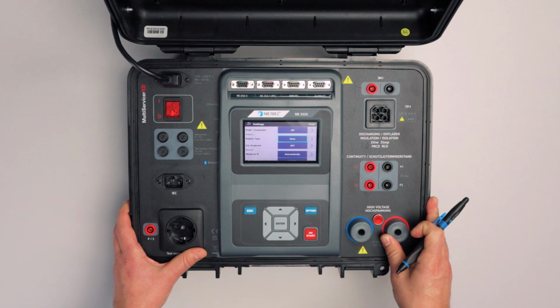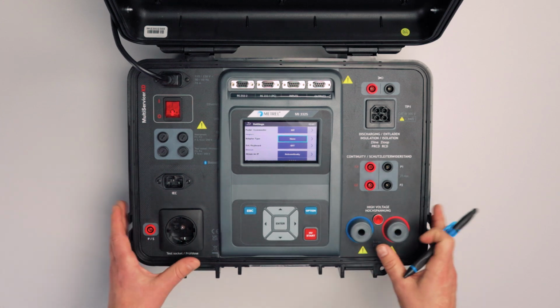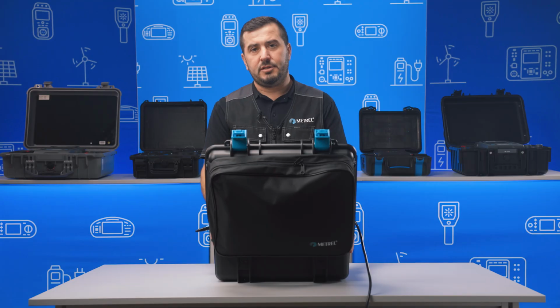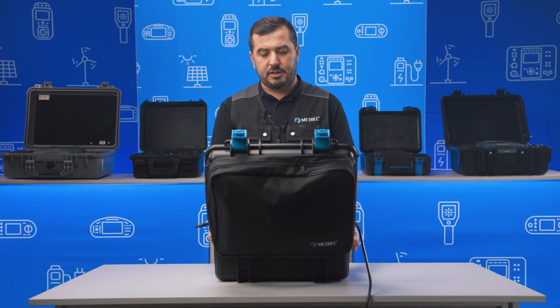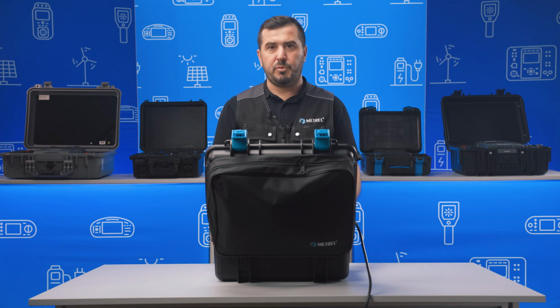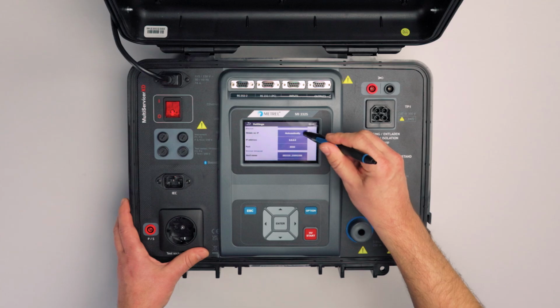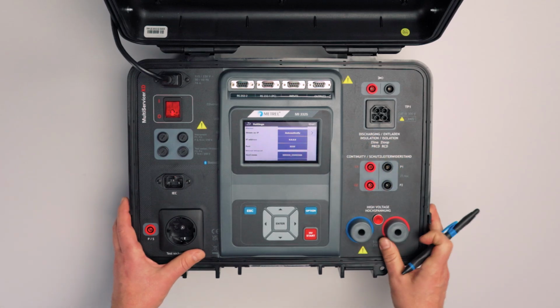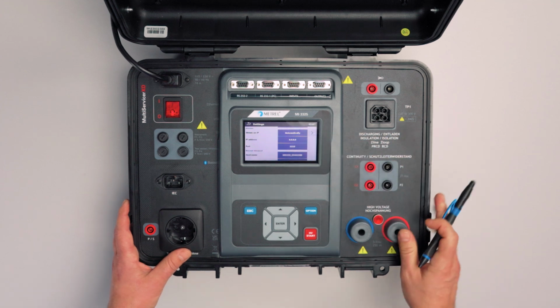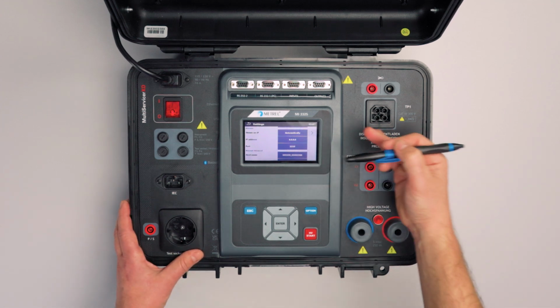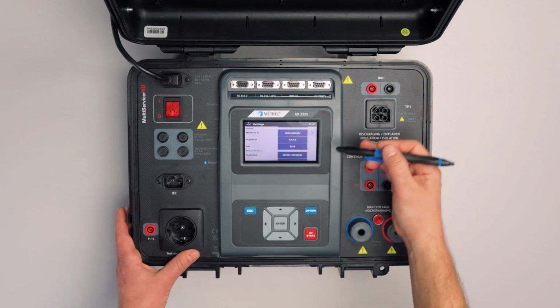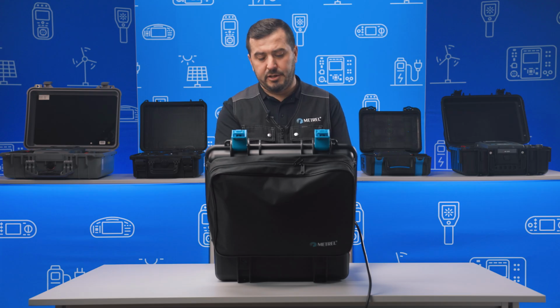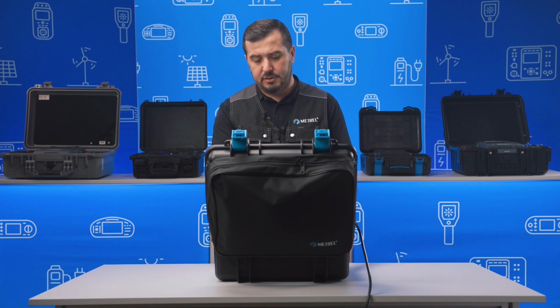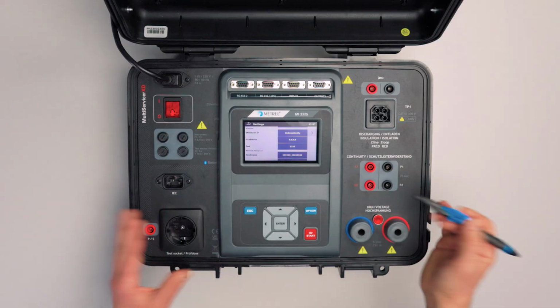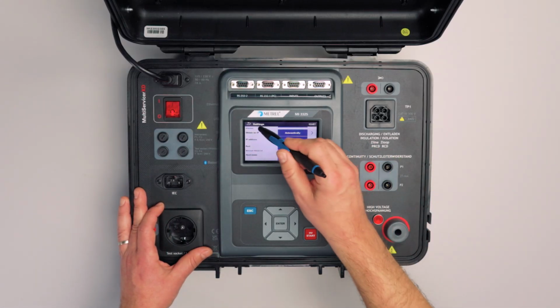Additional adapter which does not need a selection in the settings menu, it's the A1460, and that is the adapter that serves for testing of electrical equipment where we need an automized procedure. The last part is dedicated to Ethernet communication. In case that you would like to select manual setup, select manually, then dedicate all parameters, and the instrument can be connected to Ethernet via custom settings, or simply use the automatic mode.